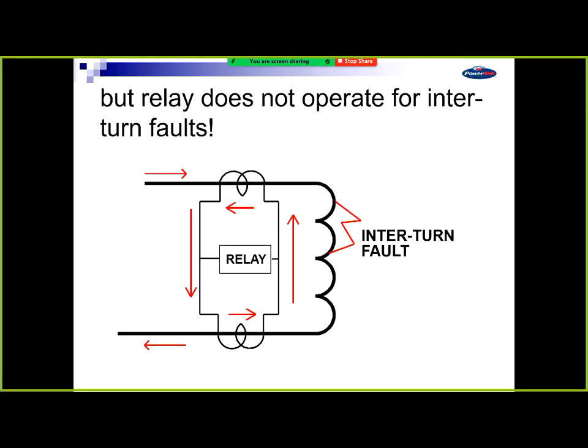You get an inter-turn fault, they don't operate for those. So you get current in the top like before, but going through the bottom as well. The current circulates in the leads of your CTs all connected together, but not through the relay, so the relay won't operate in that scenario. So they don't work for inter-turn faults. So the same A phase, having a fault between a couple of windings, it won't detect that.